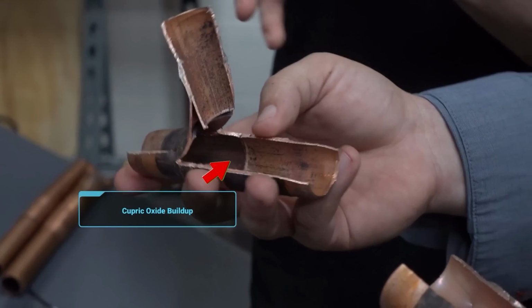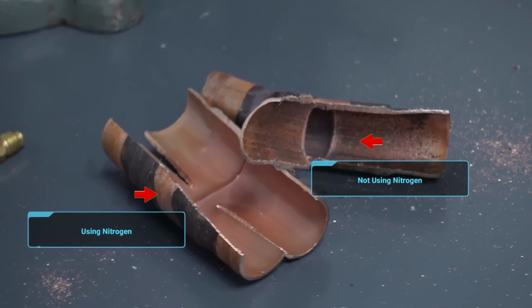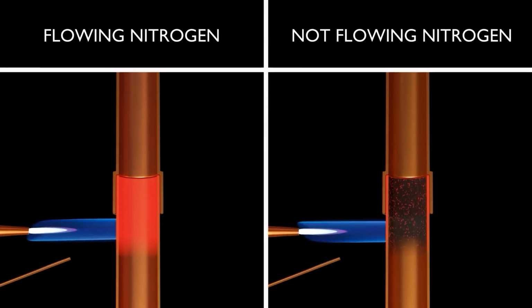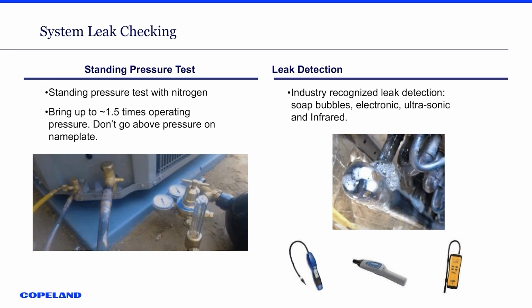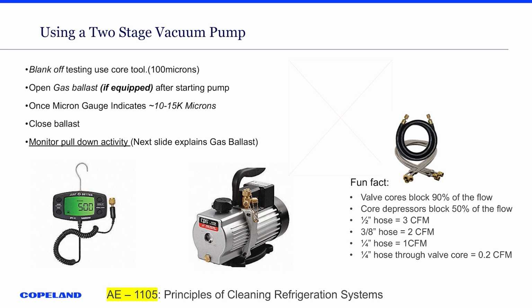And it's always been important, but now that we're starting to use these newer refrigerants, A2Ls, A3s, CO2, whatever, refrigerants that we haven't used in the past, it's going to be a lot more important, right? We have to make sure that we have no leaks in our system, right? So first we're going to braze all the pipes together, then we're going to make sure we have no leaks, right? And then what comes next in the system? What do we need to do before we put refrigerant in it? Evacuate the system, yep. So we evacuate that system. Whatever the OEM says we need to evacuate it to, usually they say 500 microns, but sometimes we need to go lower than that, right? So make sure we're doing a really good job of evacuating the system.